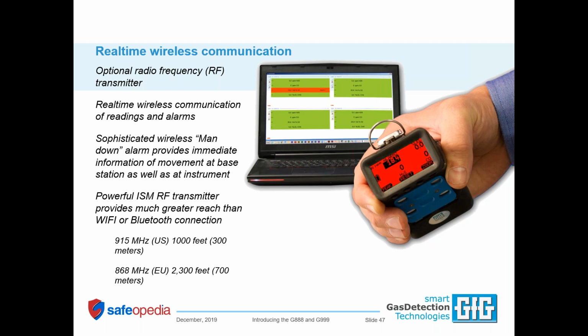The other options for wireless communication are cellular, which requires everything you need to communicate with your cell phone—sometimes that works in an industrial setting, sometimes it doesn't work so well. Or Bluetooth, which is terrific for short-range communication, but you need a collection device positioned nearby to acquire the information and send it onward. The difference is 10 meters for Bluetooth, from the Altair 4X manual, versus 300 meters with the GfG portable G888 and G999 instruments when equipped with the RF module.